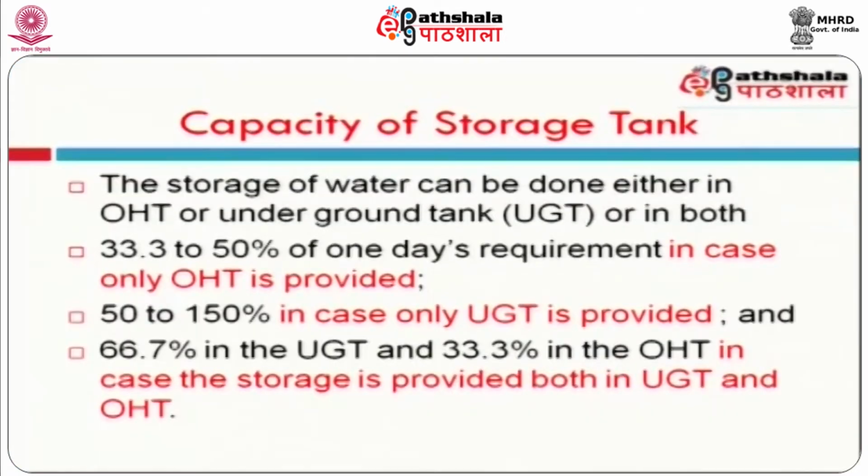In case the water is provided in the underground tank, 50 to 150% of the storage requirement is necessary, because from the underground tank we can pump the water directly to the consumer fixtures without any overhead tank. The water can be directly pumped. In that case, the water is coming from the source at a different duration, and you are supplying to the consumer at a different duration. So, depending upon the supply duration and distribution duration, we can have a storage capacity of 50% to 150%.